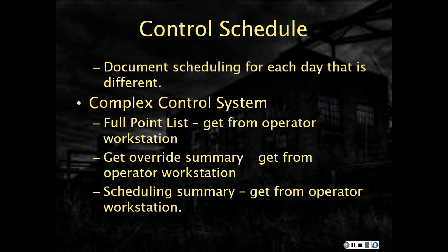We can get set points, we can get setbacks, we can get runtime of the equipment. Sometimes BAS systems are attached to maintenance, preventative maintenance programs. We can get printouts of routine preventative maintenance. We can get alarm or error summaries to see if equipment are constantly going into alarm for whatever reason. So BAS systems, building automation systems, or DDC systems, are really a wonderful goldmine of information if you happen to have them.